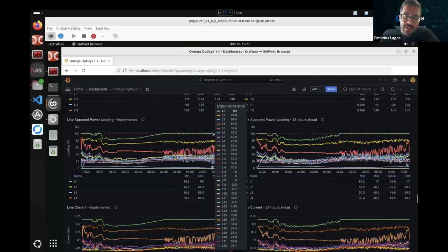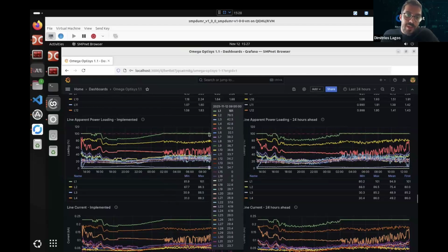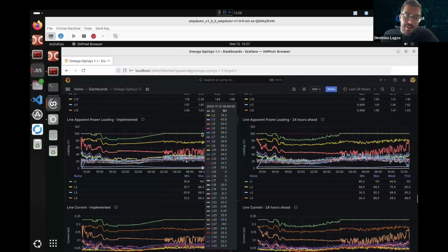And that's the actual benefit of having a centralized approach with a digital twin of the network, because you can see the impact of the different strategies, curtailing active power and using reactive power, on the whole network. A local controller would only see a local voltage issue and dispatch reactive power to resolve it, and it wouldn't know that in another line this reactive power dispatch would cause a congestion.